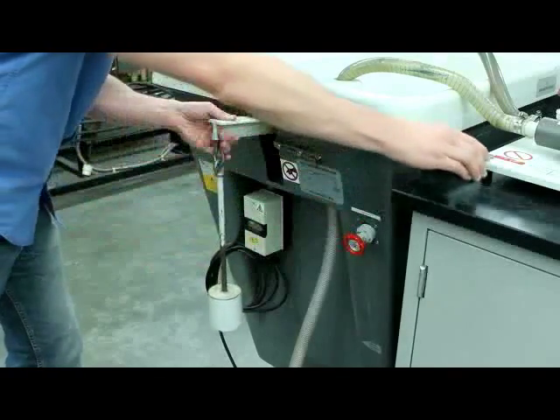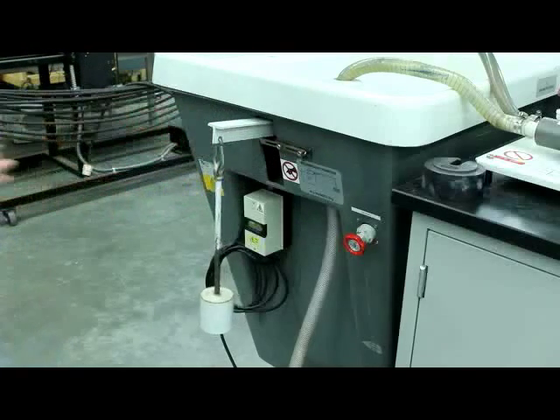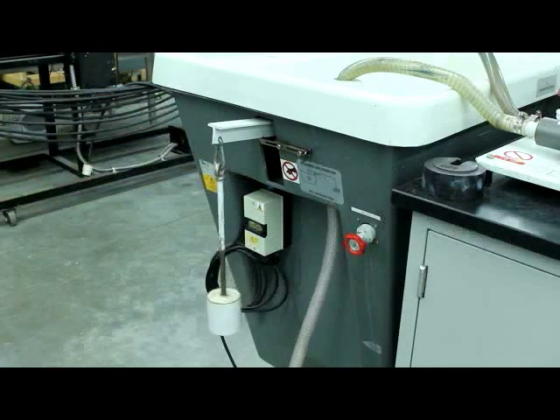When you are finished with a flow rate measurement, remove the weights from the weight carrier and allow the beam to rest on top of the metal stop until you are ready for the next measurement.